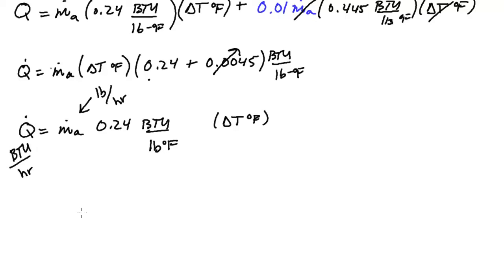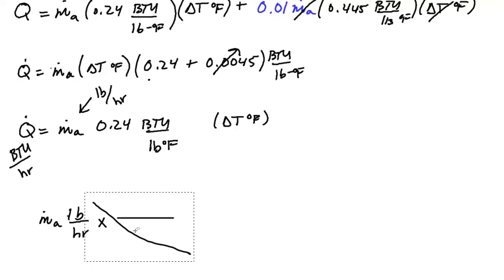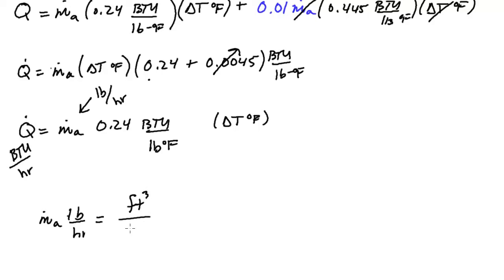So how do we do that? If we want to go from a mass flow rate of air in pounds per hour, to get to CFM, we're going to have to multiply it by some things. And the first thing is by this factor of density. Actually, let me erase this here for a second. We need to replace this pounds per hour, starting from cubic feet per minute. So if we do this, what we'll need is a ratio to get it to hour. So we have 60 minutes in 1 hour. And then we also need this factor of density to go from volume to mass.